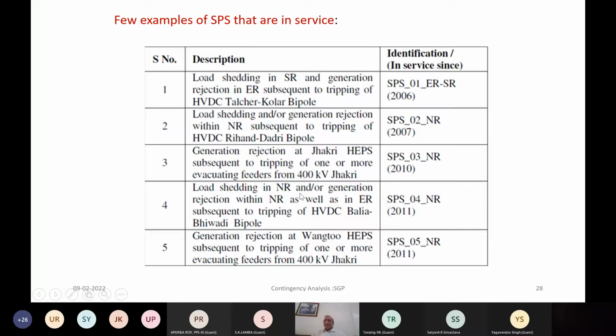Load shedding in the northern region, or generation rejection in the northern region as well as in the eastern region, subsequent to tripping of the HVDC Balia Bhiwadi bipole. This is a similar example where one power flow corridor, when it trips, you take action in a different region also. Similarly, generation rejection in the hydropower station for Jhakri.